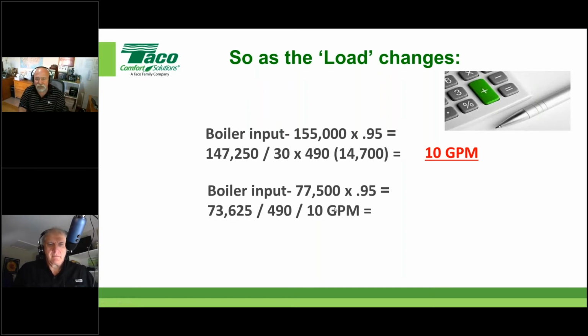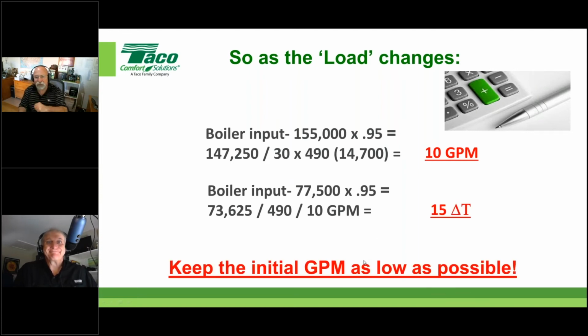So here's half again. I just took the same calculation, but now I'm using 10 gallons a minute because I know I'm fixed at 10 gallons a minute. What I'm solving for is what's going to be my new delta T. I was at 30 under full load condition, but if I keep 10 gallons a minute, what will be my new delta T? Just remember that. And the point I'm making more than anything is keep that initial gallons per minute as low as possible, and you'll get an overall system efficiency increased as best you can with a fixed speed circulator.